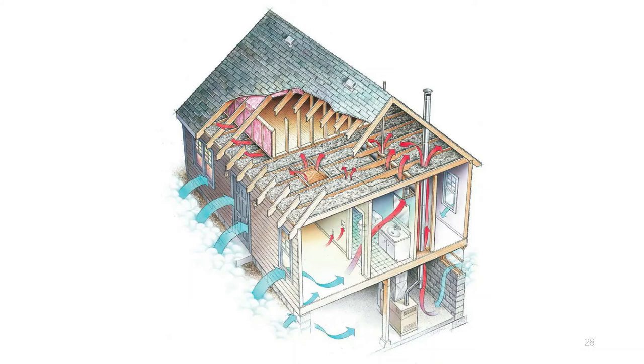Some of us rely on a leaky building for ventilation. However, a leaky building is not a ventilation strategy. Outside forces are required for air to move through the building cracks and openings. If you don't have wind, you don't have ventilation. If you don't have a temperature difference, you don't have ventilation. Leaks don't mean you get air where you need it. You wouldn't build a leaky plumbing system and assume water will go where it's needed and be removed as needed without intervention. The same is true for ventilation. A leaky building does not ensure effective ventilation, and depending on where the leaks are, a leaky building could necessitate increased mechanical ventilation. The saying, build it tight, ventilate right, exists for a reason.